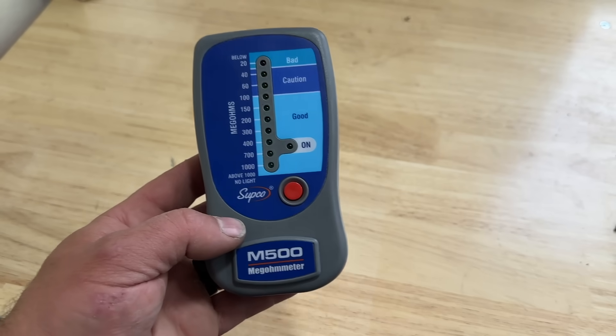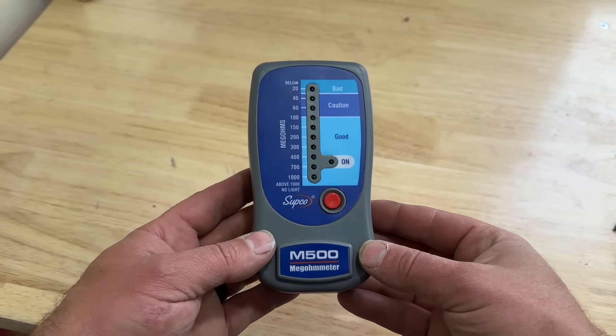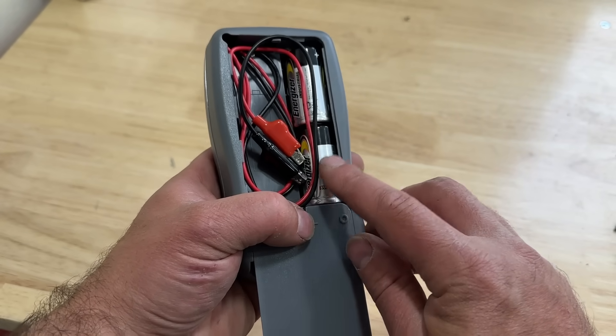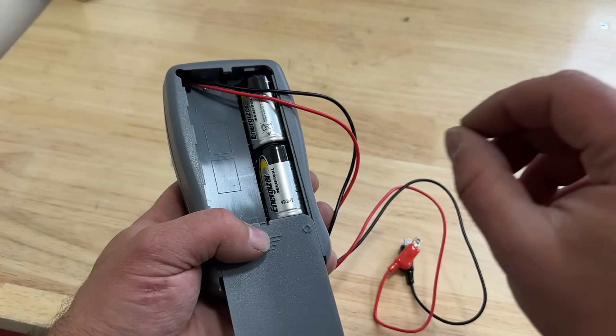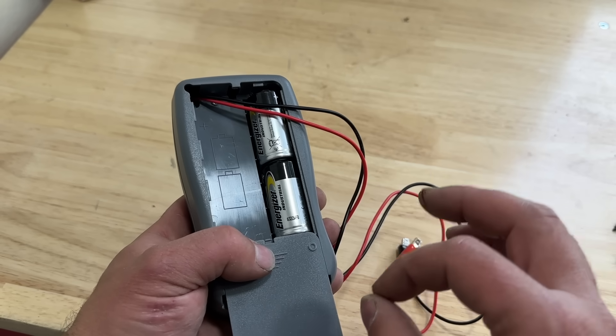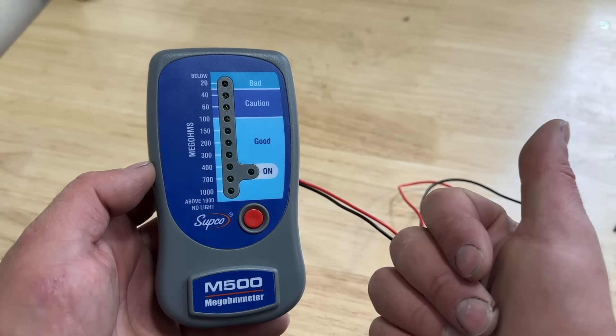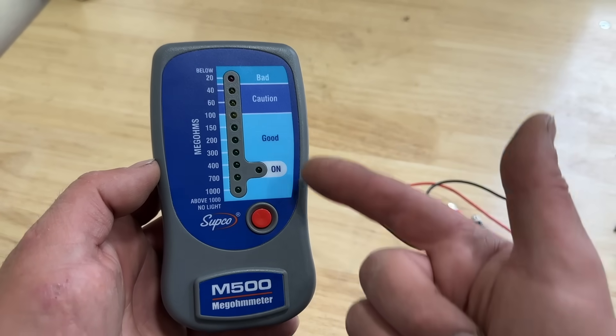Before we get into how to use this, let me briefly explain what this actually does. A megohmmeter uses a small amount of current — it takes two AA batteries, purchased separately — and sends that current through the windings of each terminal on the compressor, checking the insulation value of those windings. This tool does not lie; it tells you whether it's good or bad. We're going to check it on a relatively new system and a really old system to see what difference that makes.